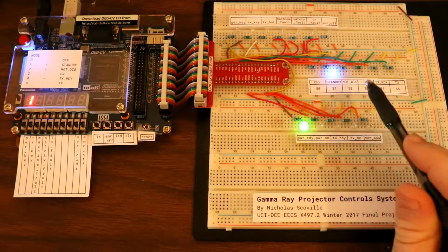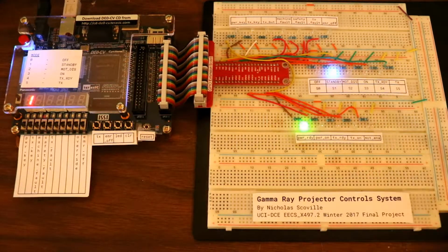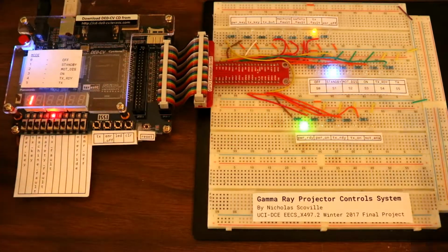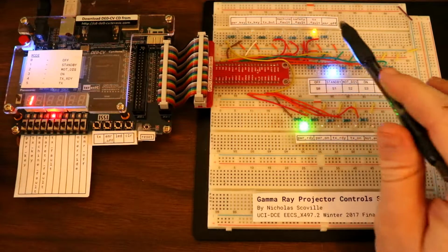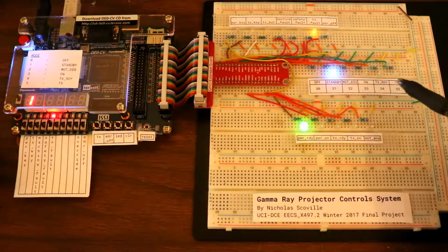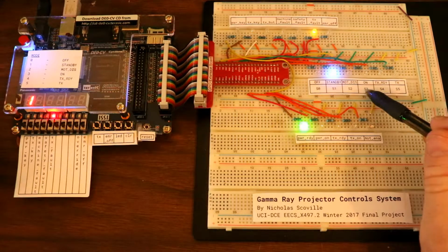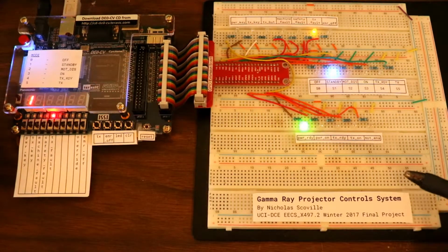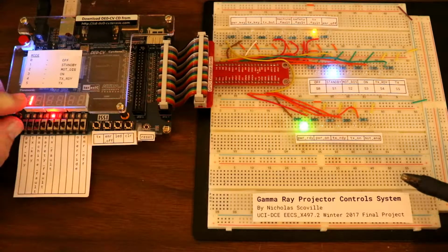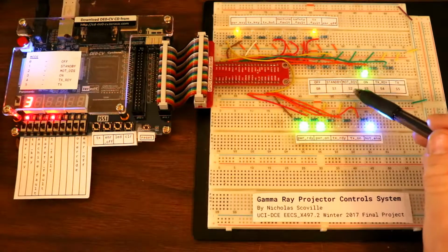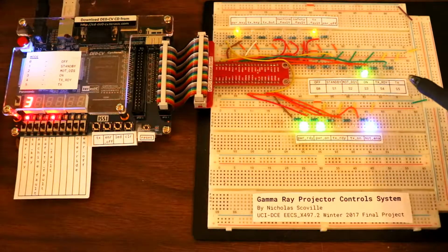To get into the on state from the standby state, you have to have two things. You need to have a transmit fault that is active, because a transmit fault will prevent the machine from going to transmit, because you don't want to go into the on state and directly to transmit when there's no fault. So now I can simulate turning the power key, and I go on to the on state. We skipped the motor disable state, but I will come back to that in a minute.